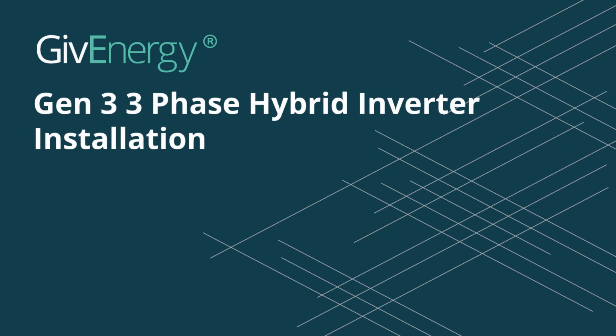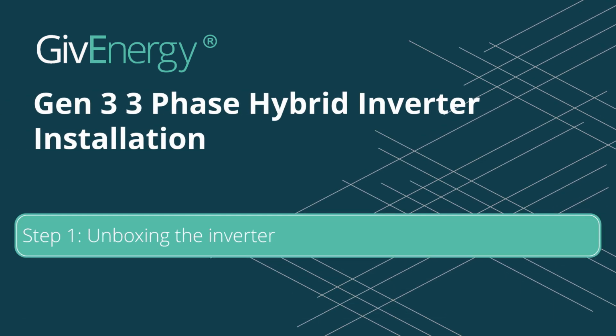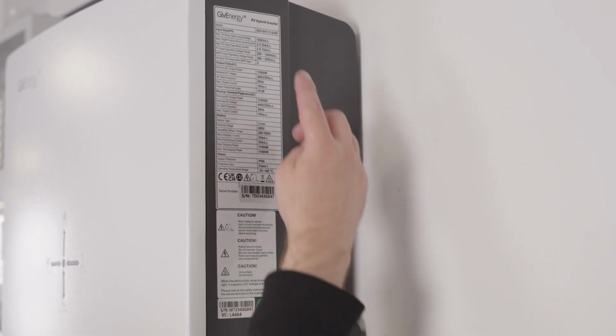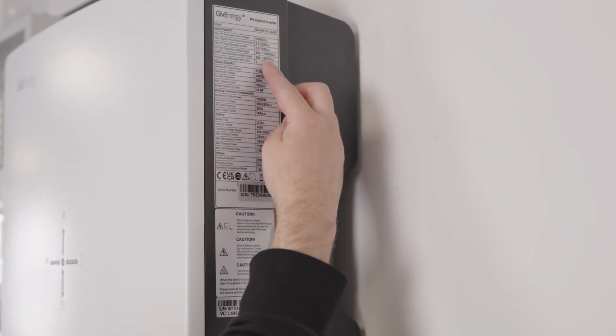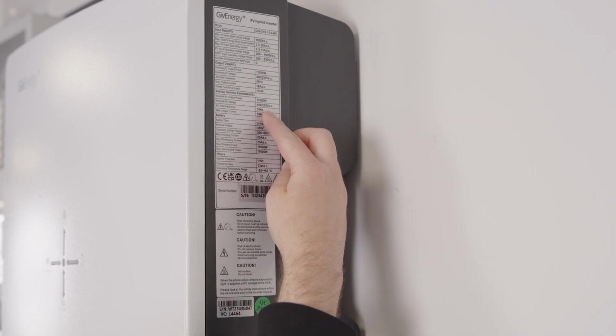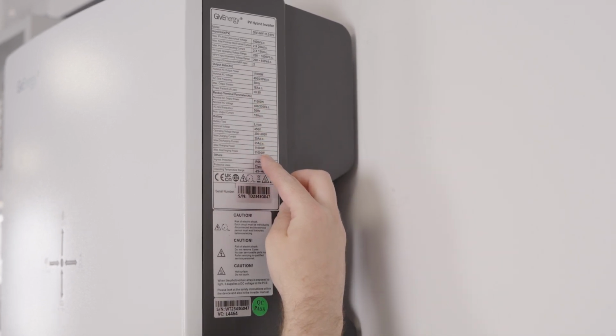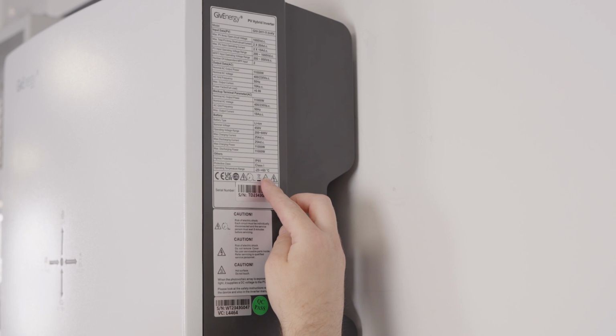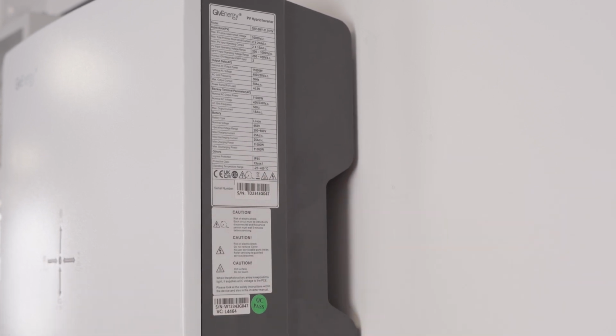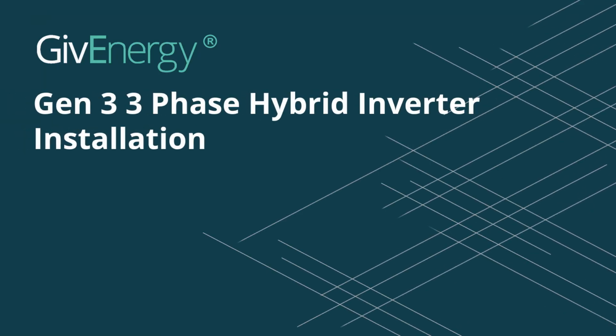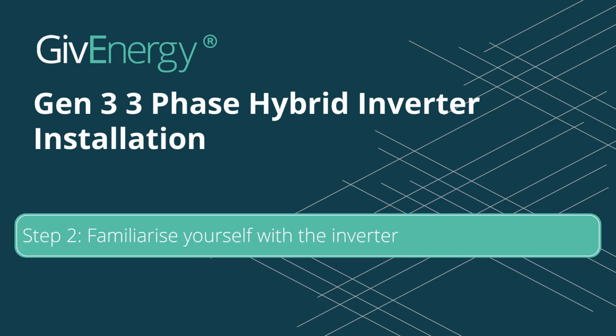This video will show you how to correctly install the Generation 3 3-phase hybrid inverter. Step 1. Checking and unboxing the inverter. Check that the model and specification of the inverter's nameplate match the order specifications. Now check the unit for any signs of damage, and if any damage is found, please contact your wholesaler or supplier immediately.